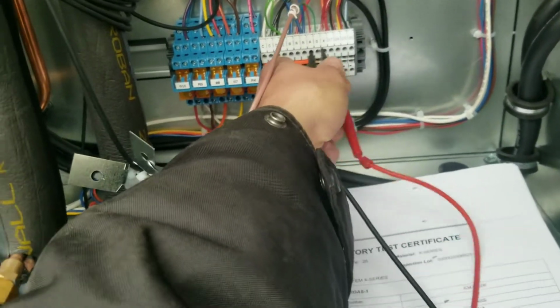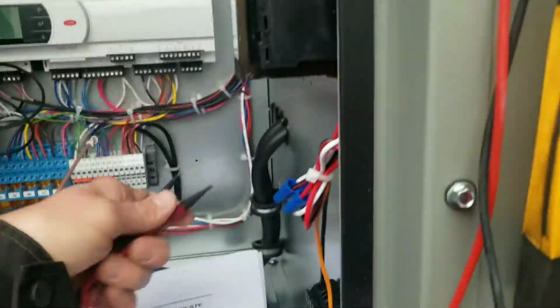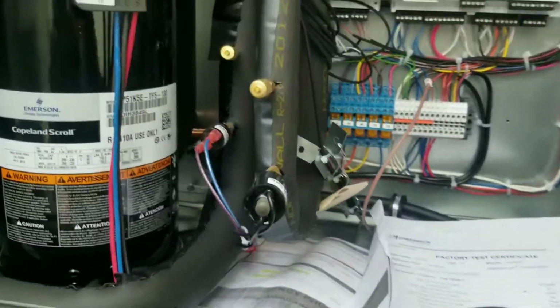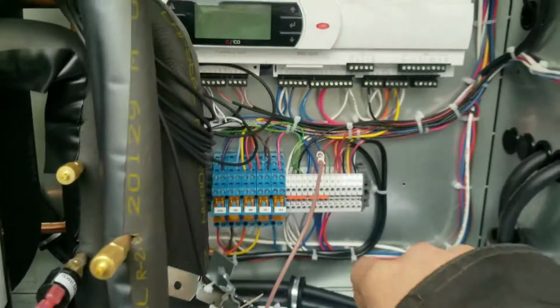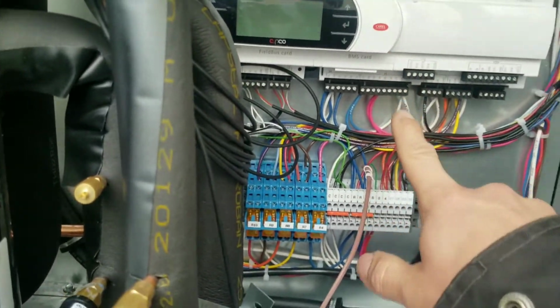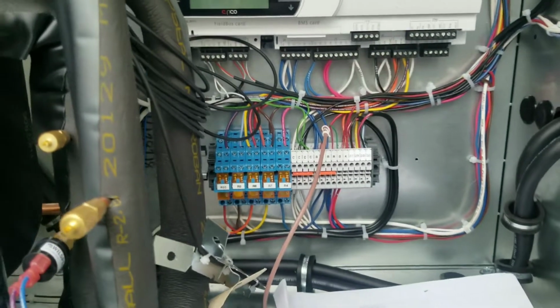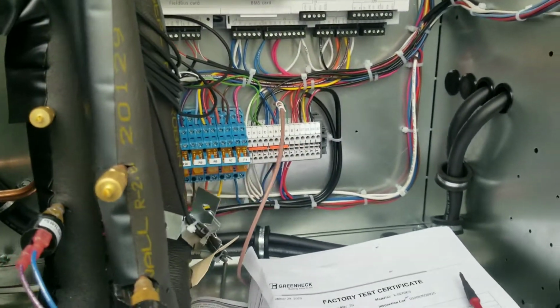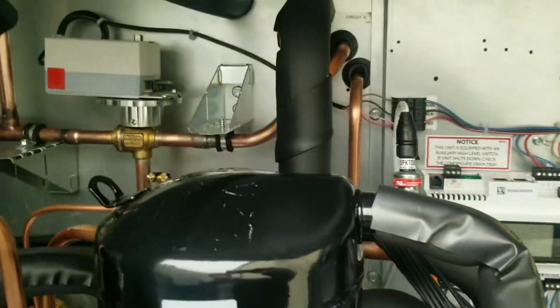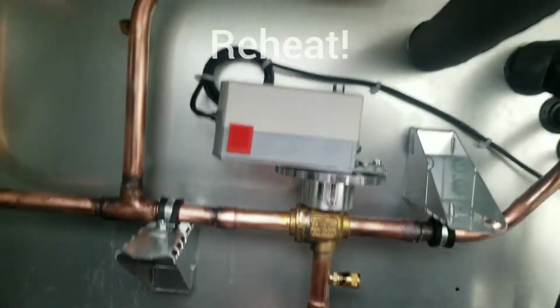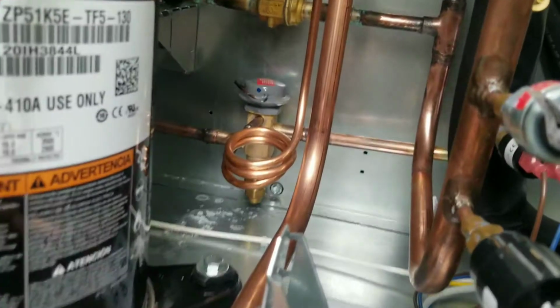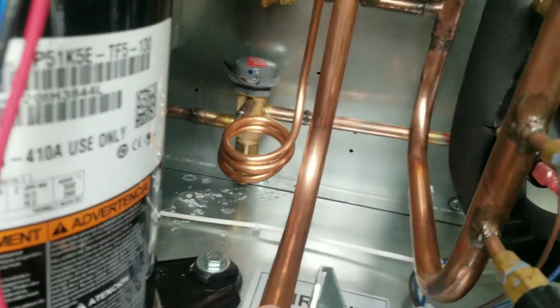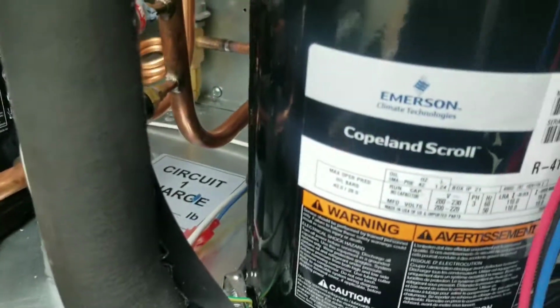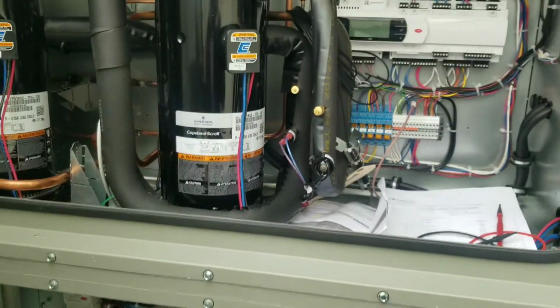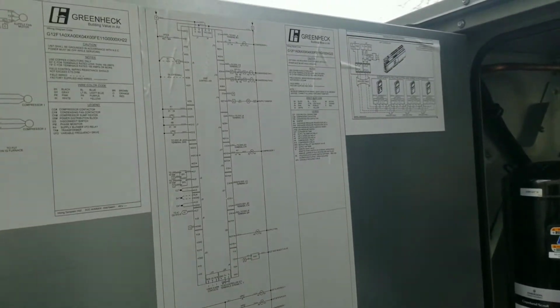Here's my signal coming from inside, and I do have a closed switch now, so we're gonna have to turn this thing on, verify rotation, and then dig into this control, and we should be able to set a discharge air temperature that it's going to try to maintain. Doesn't look like a bad little setup here. It's hot gas. It's like a headmaster, head pressure control. Alright, well, let's check our phase and dig into this thing and see if we can learn something.